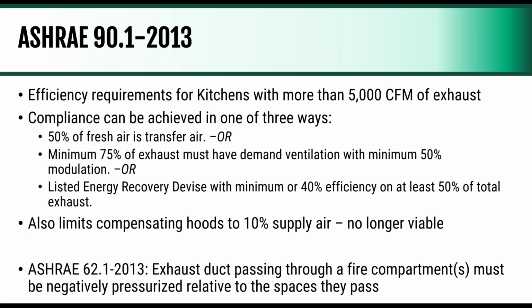A side note on 90.1, it limits compensating hoods to 10% supply air, which we don't know anyone who can make a compensating hood be effective with 10% supply air. So it's basically meant that compensating hoods are no longer viable for commercial kitchen ventilation. Another part of ASHRAE 62.1, and this is kind of creeping through, different municipalities are getting more stringent on it, but exhaust ducts passing through fire compartments must be negatively pressurized relative to the spaces they pass.